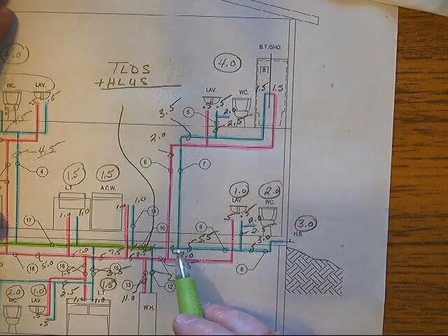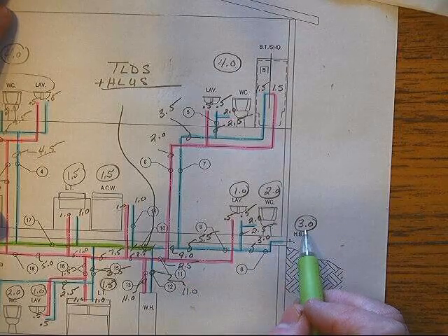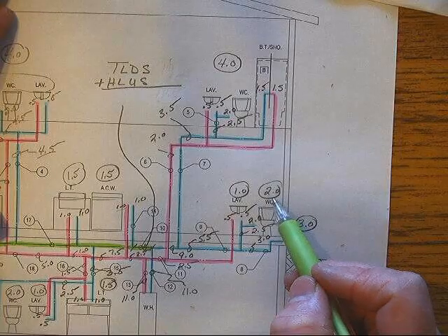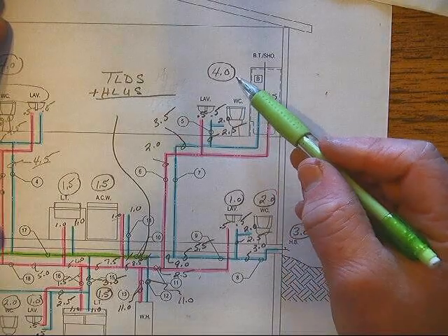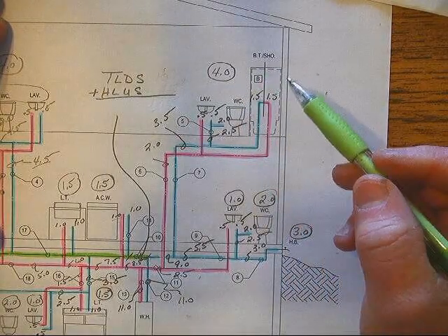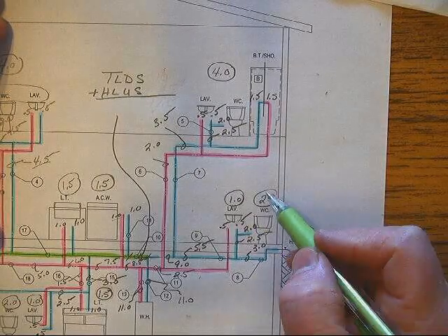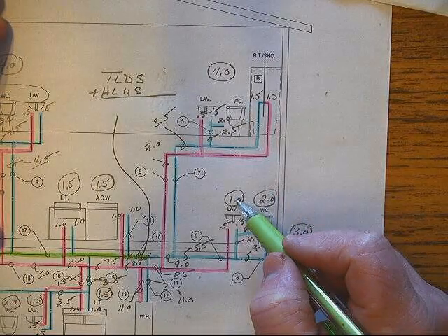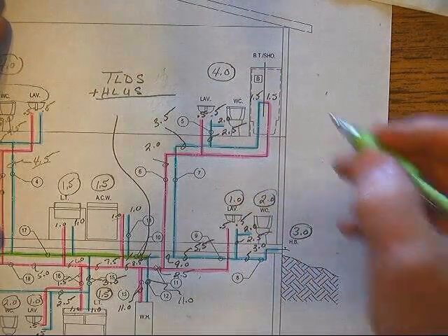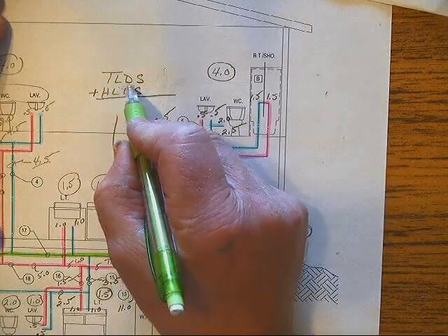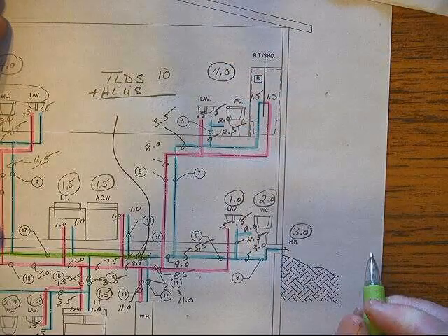As I follow that water distribution piping downstream, I locate a hose bib, I locate a flush tank water closet, the lavatory, and then of course upstairs I locate the bathroom group. So when I add 3 from the hose bib, 2 from the water closet, 1 from the lav, and 4 from the bathroom group, I get a total load downstream of 10 WSFU.